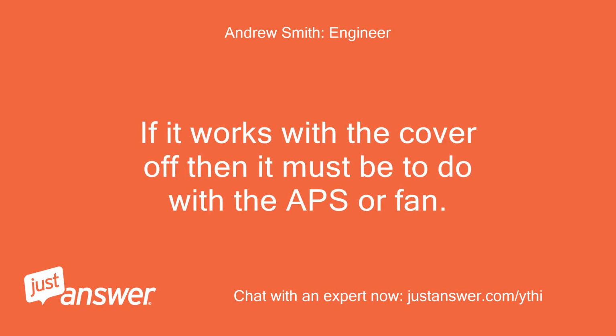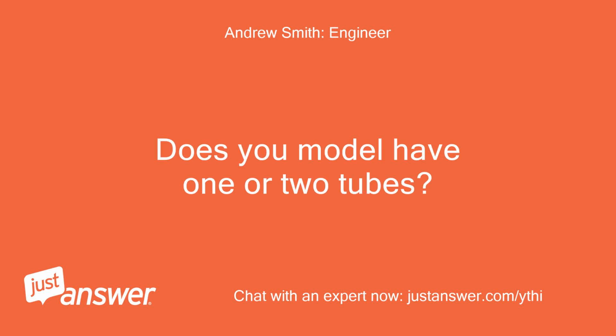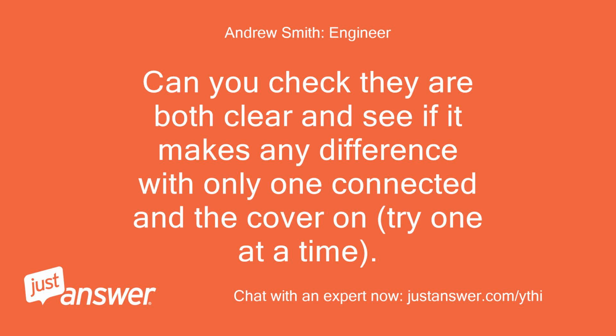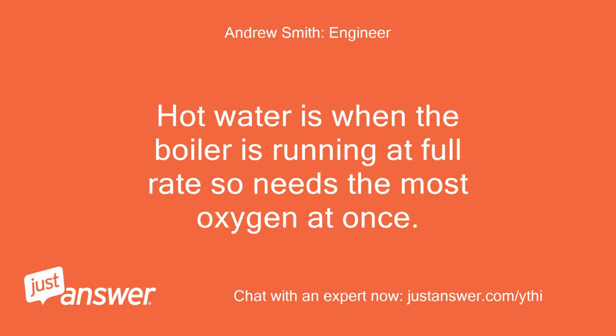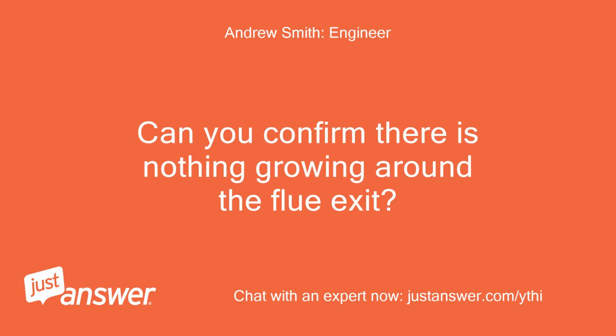If it works with the cover off, then it must be to do with the APS or fan. Does your model have one or two tubes? Can you check they are both clear and see if it makes any difference with only one connected and the cover on? Try one at a time. Hot water is when the boiler is running at full rate, so needs the most oxygen at once. Can you confirm there is nothing growing around the flue exit?